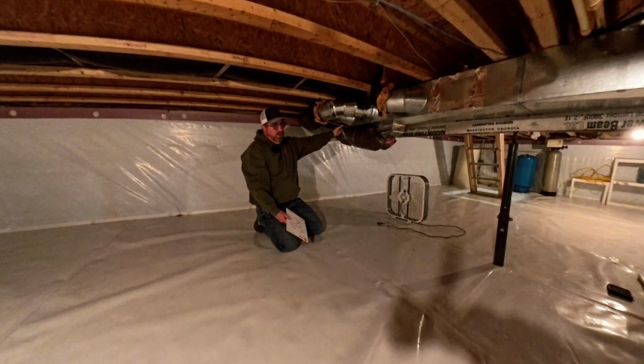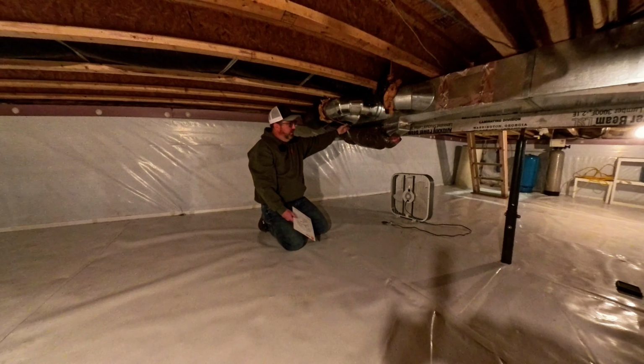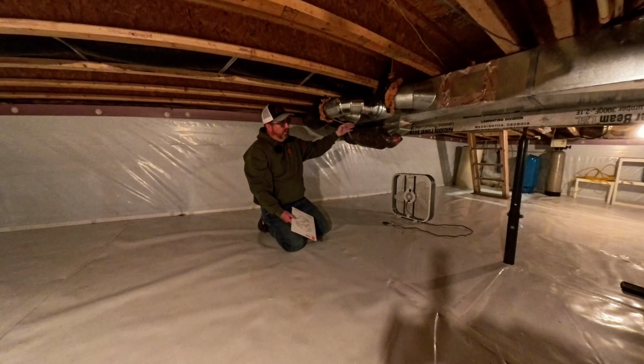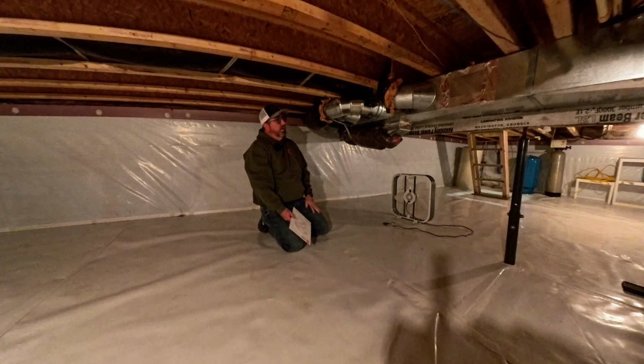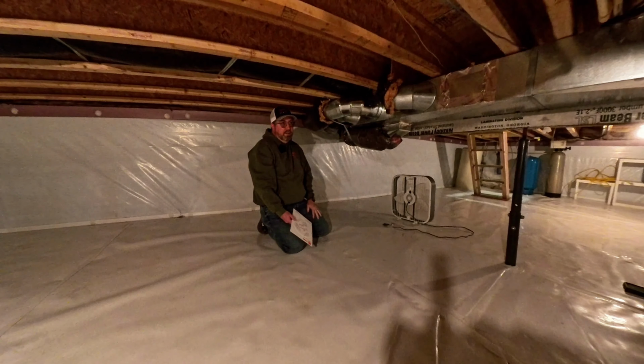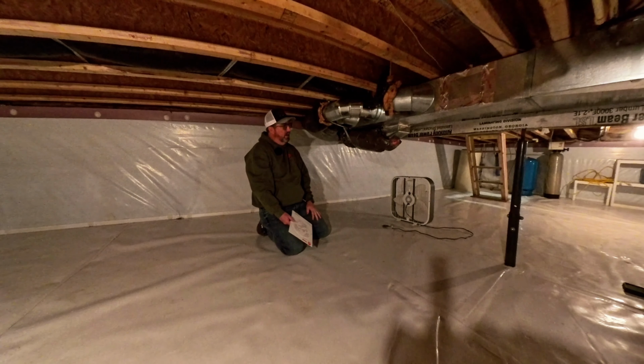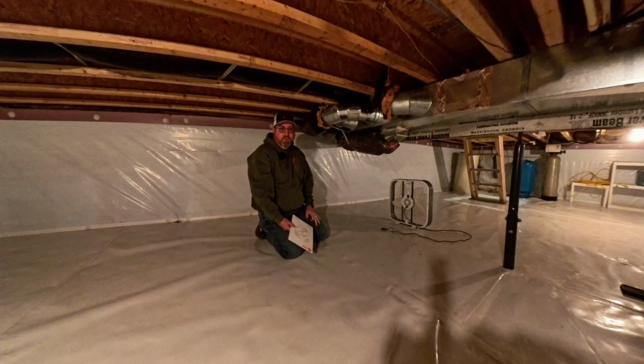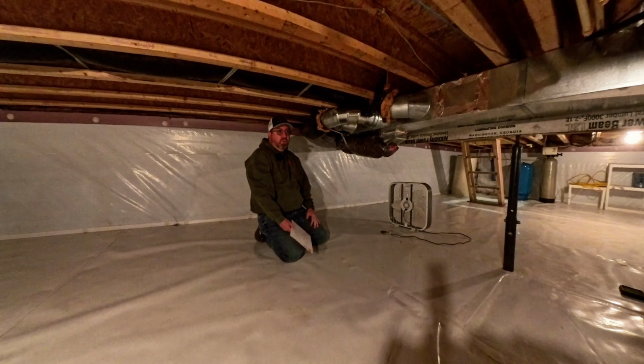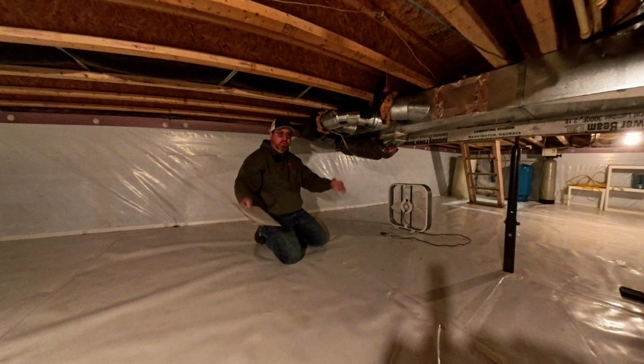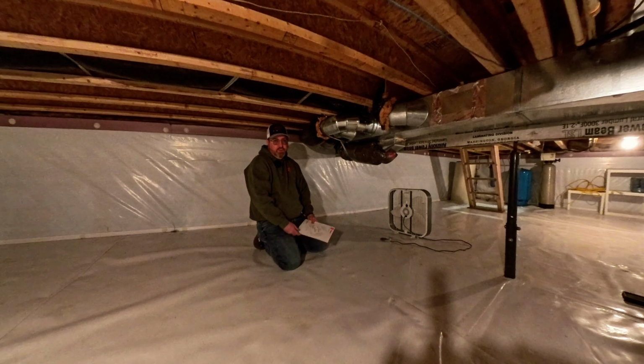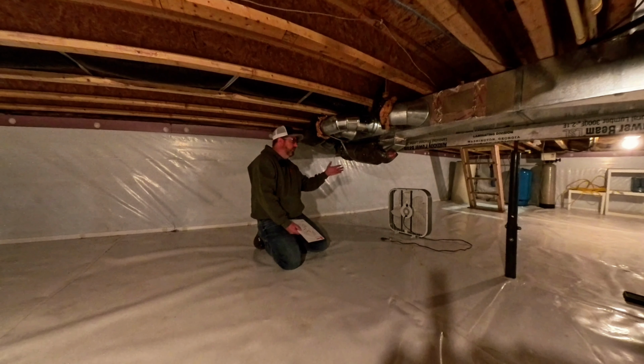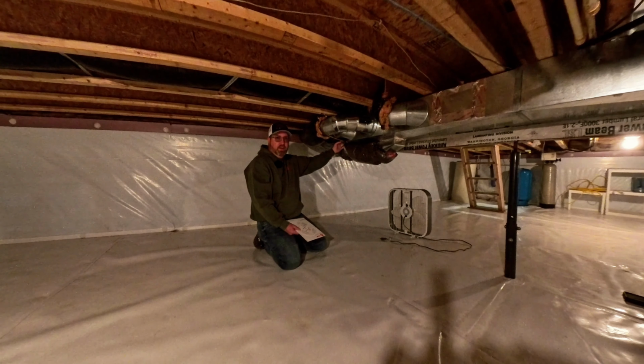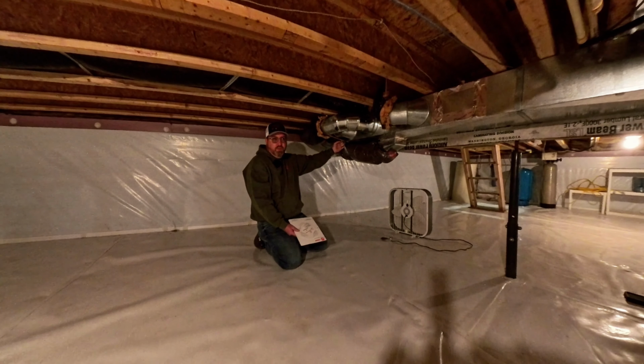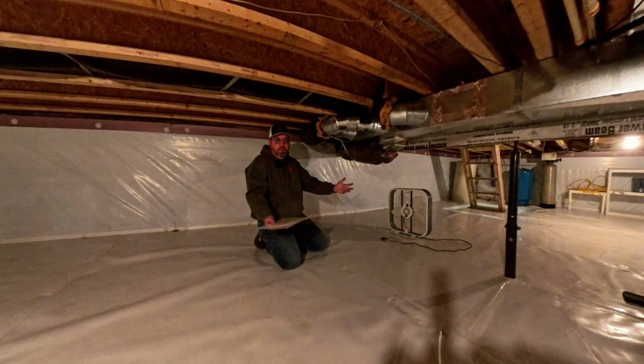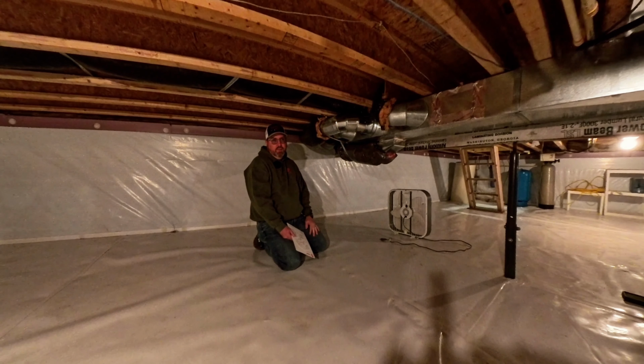So what we did is cap off the duct system like it should be, and relocate the supply runs to the side or the bottom. There are quite a few down here at the very end, but that is just how this house was built, and we've made these adjustments to make airflow better. He should see more even airflow out of all the registers together. Probably also the temperature in rooms too, because if you've got one particular room that has 2 of these runs out of the end cap, that room can either overheat or overcool, while the other rooms are not conditioning as well because they're not getting proper airflow.